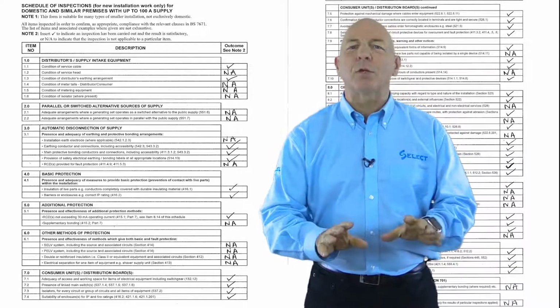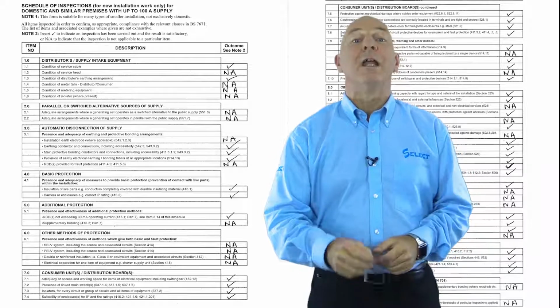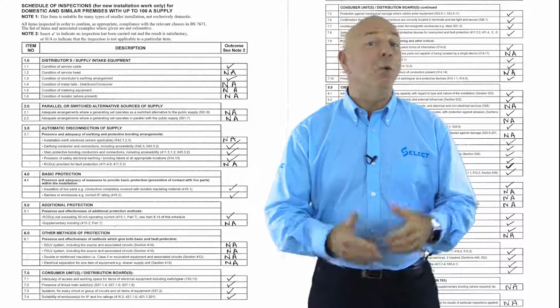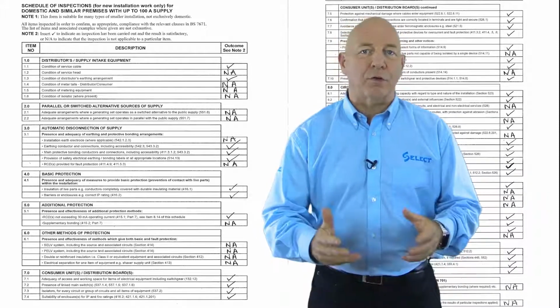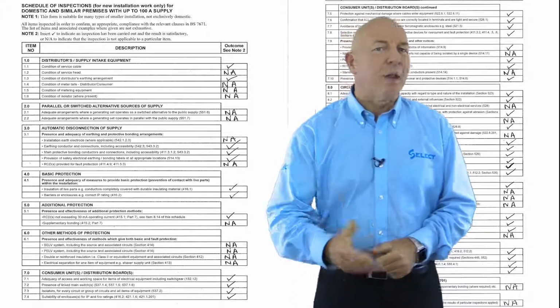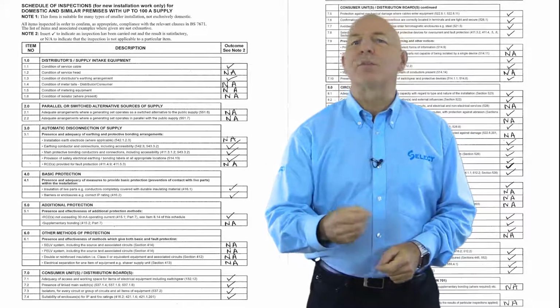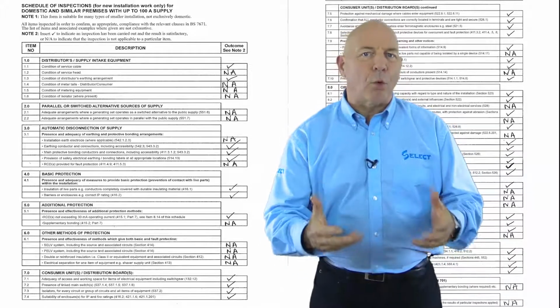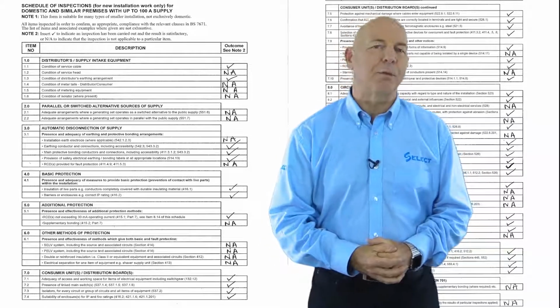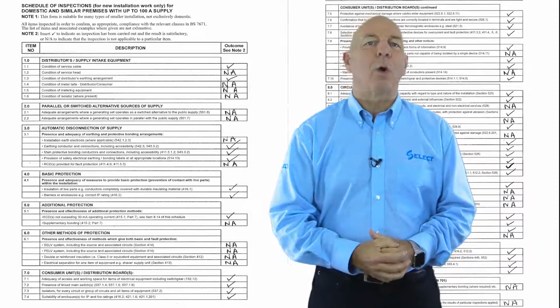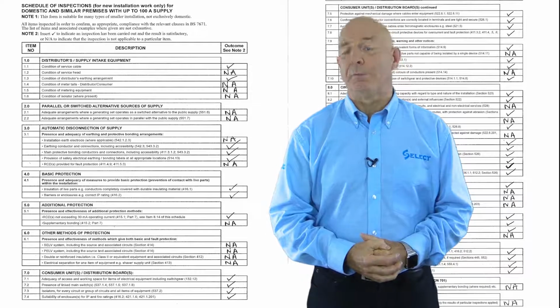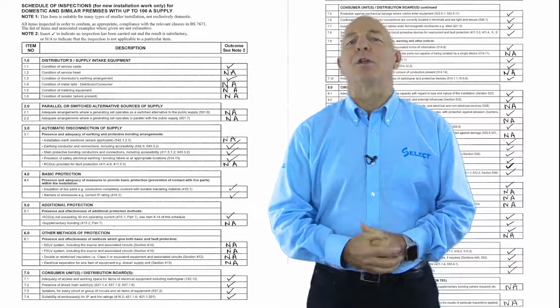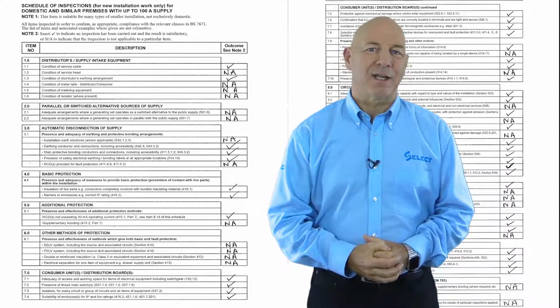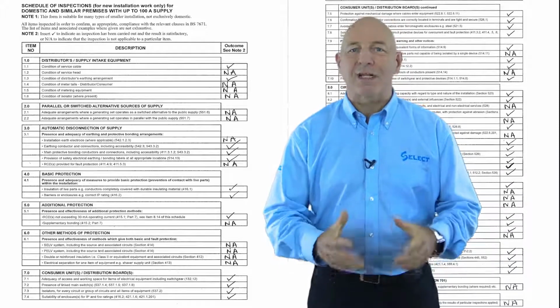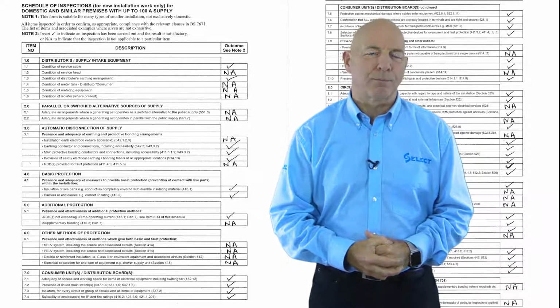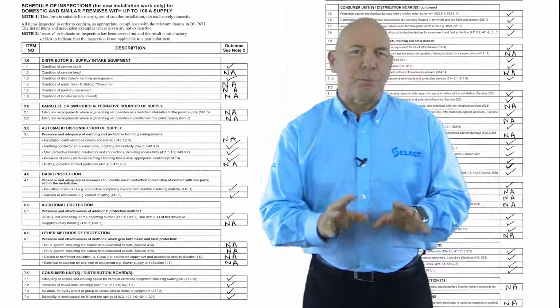In this situation, the inspector will require to be confident that work has been installed in accordance with BS 7671 and will need to carry out inspections at all stages of construction to verify that the work is compliant. For example, the inspector would need to be on site to inspect the work at the first fix stage before work is covered over or buried within the fabric of the building, and during second fix stage while electrical accessories and other equipment are being installed. A final inspection should be undertaken before any testing is undertaken to ensure that work has been completed as per Regulation 611.2. Okay, so that concludes this brief introduction.